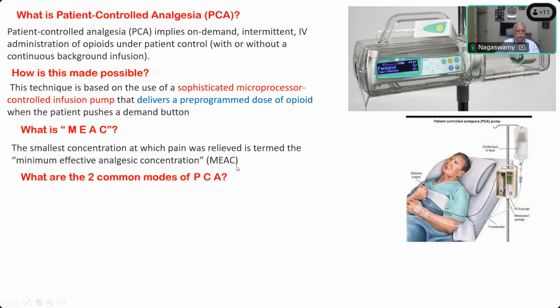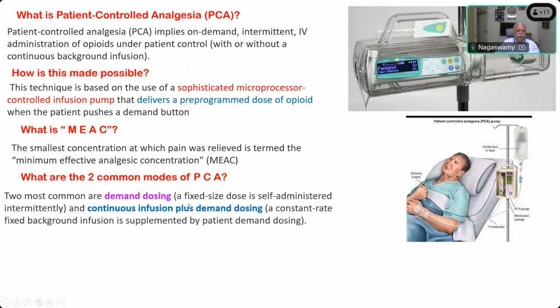And there are two common modes of PCA that are commonly used. One is called the demand dosing, where a fixed size dose is self-administered intermittently by the patient. And the second is a continuous infusion plus a demand dosing. Just like your insulin being secreted as a basal dose in our body, plus a surge during every meal, you will have a constant infusion going on from the infusion pump. And in between, if the patient feels pain, he can push the button and then get another bolus dose. So a constant rate fixed background infusion is supplemented by patient demand dosing by pushing the button, but at a particular interval. That is a very important thing.